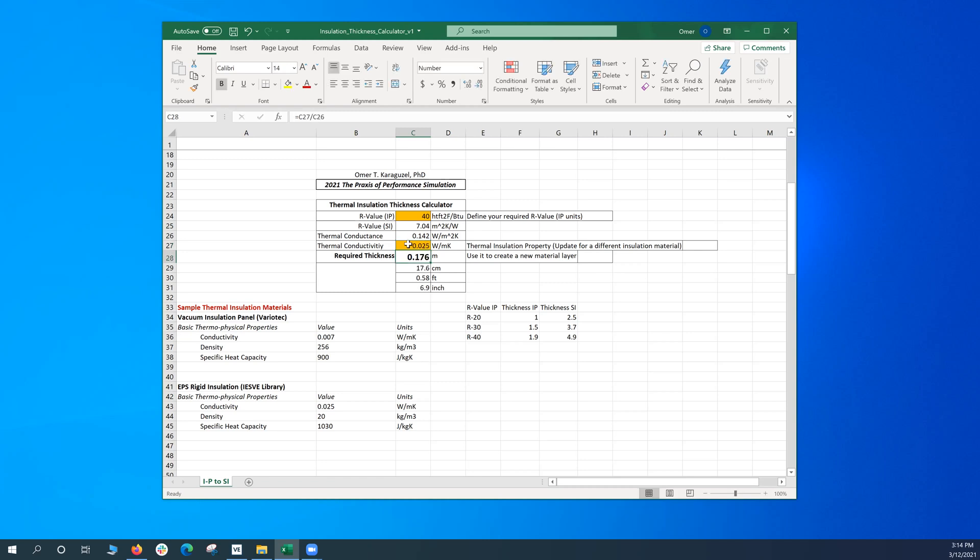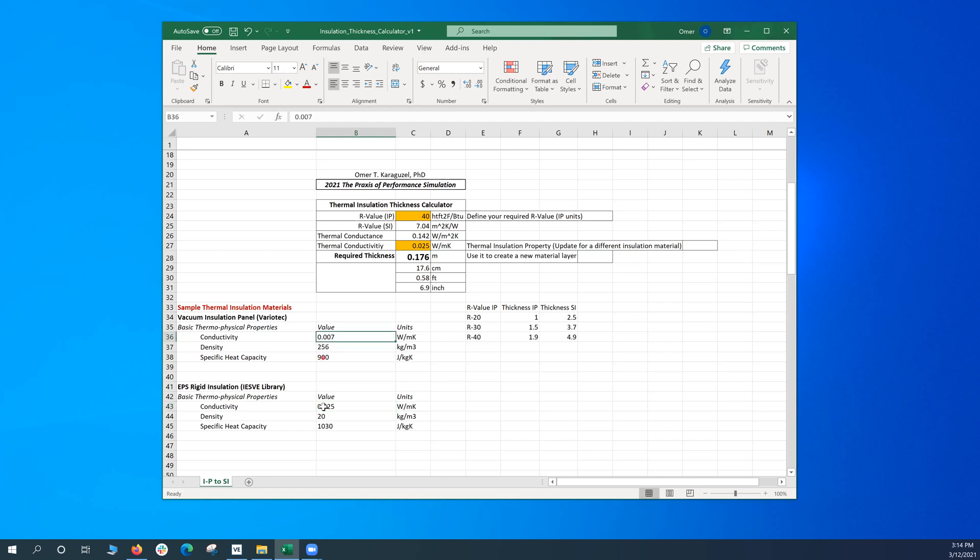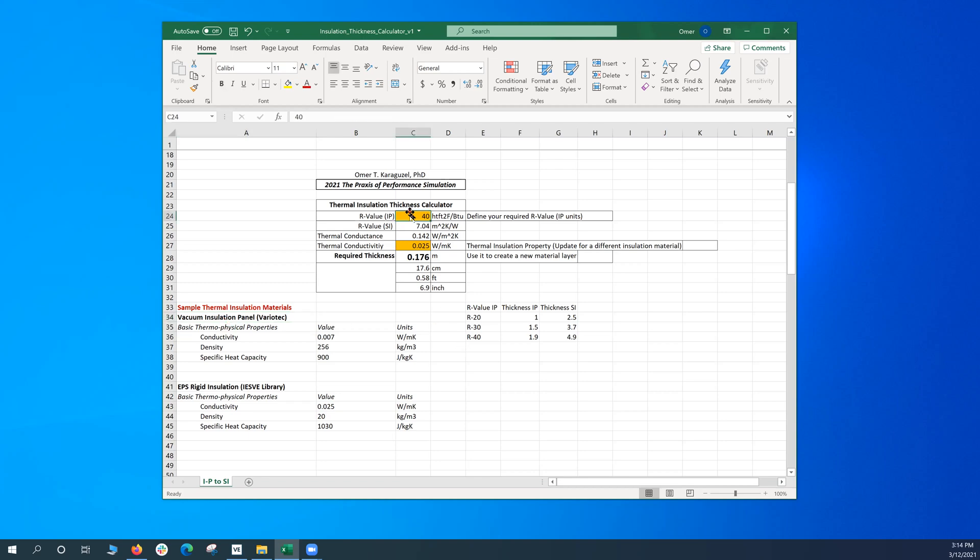17.6 centimeters. You see the increase, right? More than three times. And as you see, you see the impact of thermal conductivity on the required thickness, because I'm keeping my R40 target unchanged, but I'm going to a thermal insulation material which has a much higher conductivity as compared to my vacuum insulation. So you can try different options.